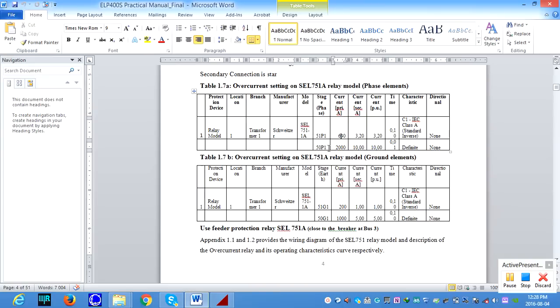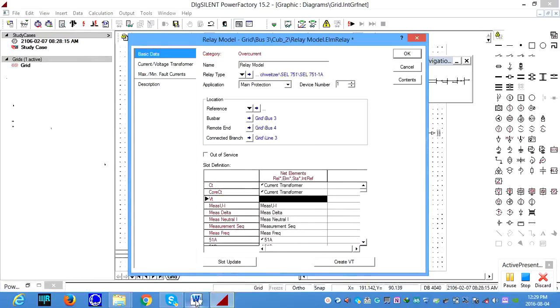So if you look at the element, we have a stage 1 and stage 2 in phase elements. The same thing for ground element as well. The idea behind here, the stage 1 will show you your inverse characteristics, and stage 2 will expose the definite characteristics. Okay. Let us consider this scenario. For instance, the phase element, you can see the current in the primary and the secondary. We can see for this primary current, or maybe the secondary current, is 3.2 amperes and 10 amperes is for the definite current. Let's give an example quickly.